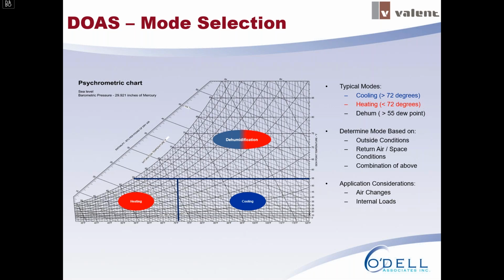And to add complexity, the amount of air changes per hour you're doing could affect the unit operation. You might need more or less capacity at a given time, and also internal loads, of course, affecting what the sensors are reading and what the unit is being called to do. So it's a very dynamic space, very dynamic conditions that are happening. And the DOAS unit is sized to handle those.